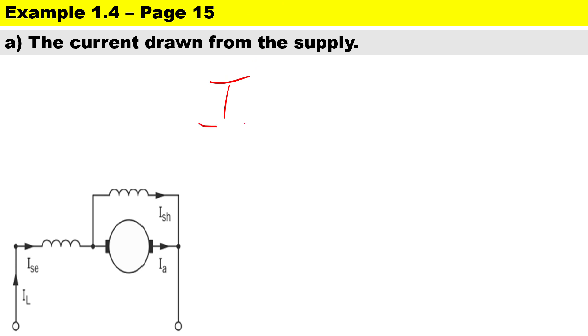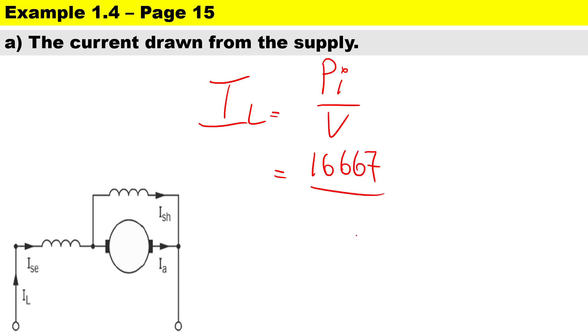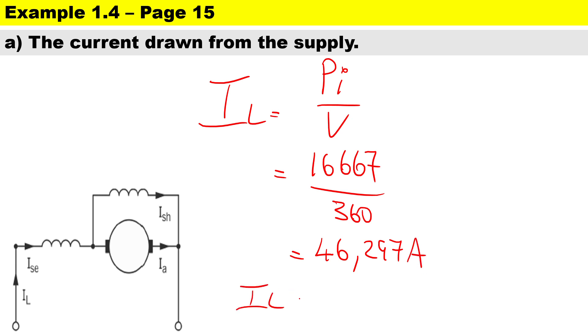To calculate the line current IL drawn from the supply: IL = input power divided by terminal voltage = 16,667 divided by 360, which gives IL = 46.297 amperes. It is important to note that IL is the same as the current through the series winding.